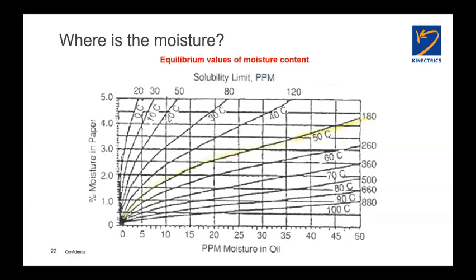This chart is, depending on which version you look at in history, either a Jeffreys curve or an Oommen curve or a Weidmann curve. What it is, it's relating the moisture content in the oil with the moisture content that is in the paper. And we see different operating temperatures for the transformer on these different lines. And I want to emphasize that these charts assume thermochemical equilibrium inside the transformer, a constant state of affairs, if you will, which almost never happens.